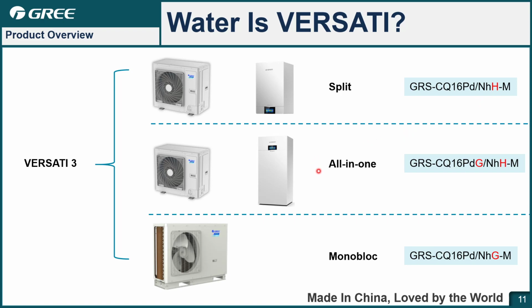Another type is the all-in-one type, which is different from split. For the split type, the hydro box and the water tank are independent. However, in the all-in-one type, we integrate the hydro box and the water tank together. So you can see this is a water tank integrated with the hydro box. In the nomenclature, if there is G and H, that means the all-in-one type. Except for the previous 2 types, we have another one, monoblock, which means the hydro box is in the outdoor unit, and the design sequence code is G. That's the basic information of VERSATI 3.